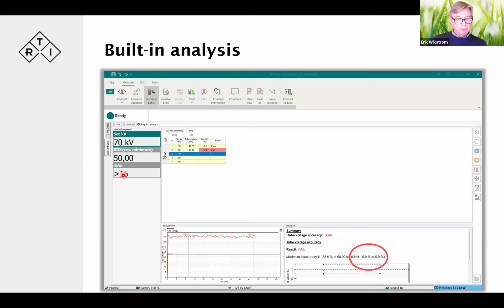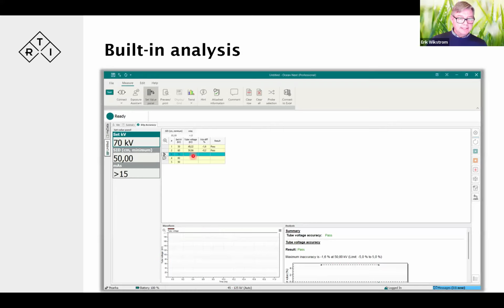All right, what do we do? Well, we go back, redo the exposure with the correct technique, and we'll then see that, okay, it passes once we have it correct. It's within the ±5, and we've passed. We're all good to go, and ready for 70 kV, which is the next set value that next station we're to test.